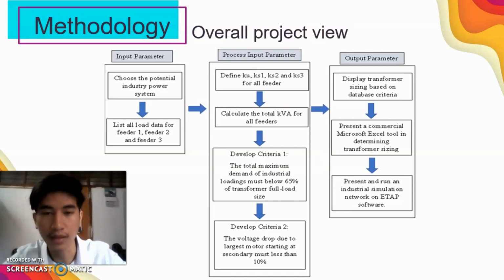Then the transformer rating must fulfill 2 criteria. Criteria 1, the maximum demand for industrial loading must be below 65% of transformer full load size. And criteria 2, the voltage drop due to the largest motor starting at secondary must be less than 10%. And for the output parameter, we need to display transformer sizing based on these 2 criteria and present a commercial Microsoft Excel tool in determining the transformer sizing, and present and run an industrial simulation network on ETAP software, which is for the normal load analysis and for the fault analysis.